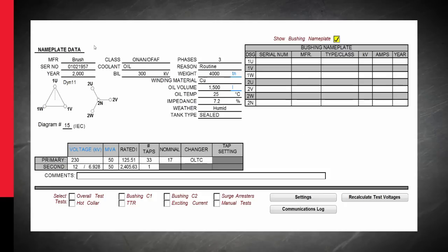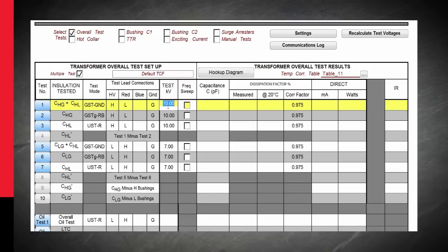We are now required to fill in nameplate information on our two winding transformer form. This includes critical information such as oil temperature, required to evaluate test results. Next, we check off our overall test. We ensure that the proper test voltages are set for both high side and low side testing. Once properly set, we depress the test button and test sequence will begin.